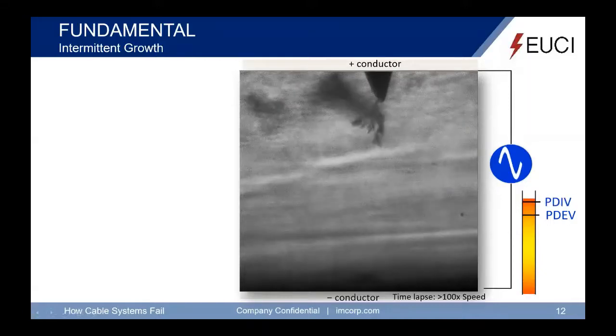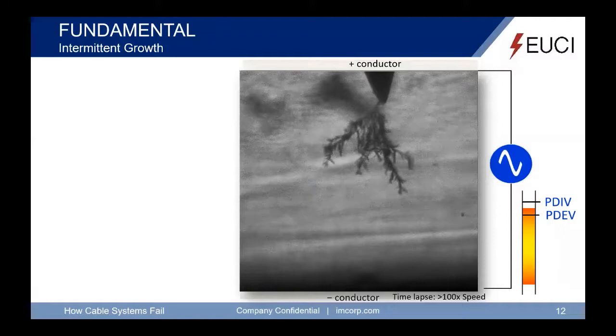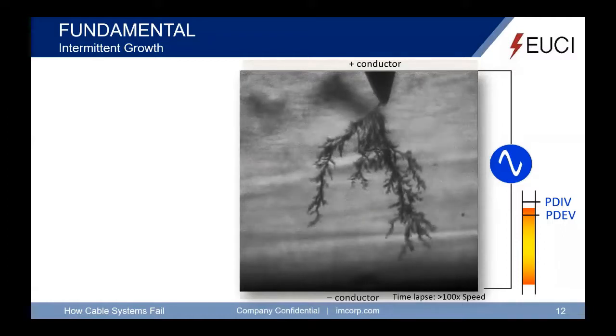Once it hits inception voltage, it's going to grow the carbon path to the inner conductor. Once it hits extinguished voltage, it'll stop growing. With more transients in the system, it begins to grow. Once we do not get to the level of extinguishing this electrical field, it's going to continue to grow until the carbon path is complete and the cable goes to failure. So that's when we talk about partial discharge inception voltage.